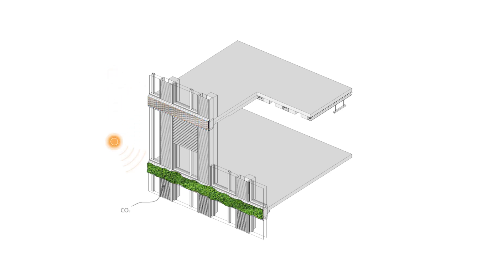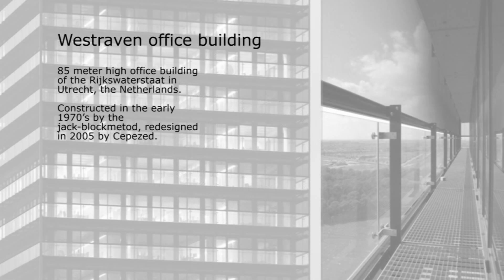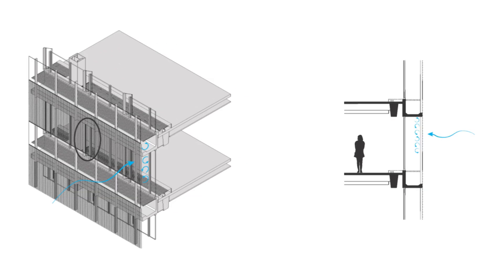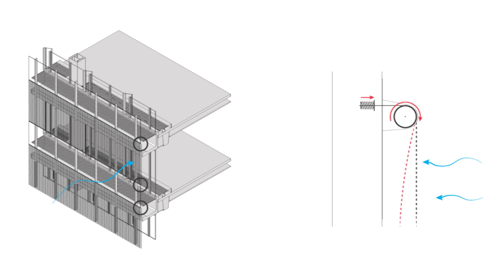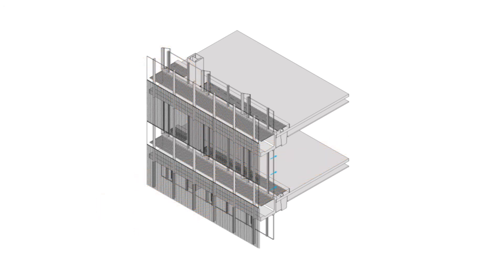Parts of greenery in the facade turn carbon dioxide into oxygen. The Westraven office building was built in the 1970s and redesigned in 2005 by Cepezed. Like other high buildings, it captures a lot of wind. By using a tapered and flat facade, this wind is broken and enables the user to open windows, as seen in this section. Tension is held on this facade by using a spring system, which also prevents the mesh from being damaged by the wind. This mesh facade also reduces the amount of sunlight by 50%. An induction system prevents cold drafts, and a climate ceiling cools down the building in summer.